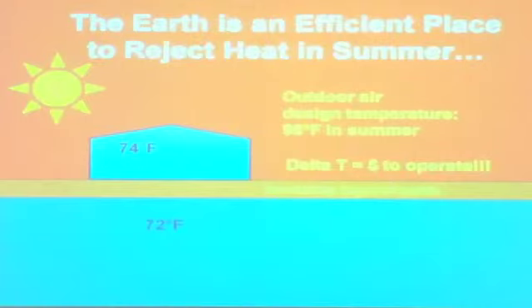Is that distance a function of the wells not sharing heat or isolating? Are you isolating the wells? Is that why you need so much? No, that's the thermal mass that it takes. Now the distance that you put those loops, the plastic tubes that were shown in that picture, the distance apart those are is based on the imbalance between the load profile of the building. The thermal mass is still the same. How far apart you put them is based on how imbalanced your loads are and how conductive the soils are, how fast heat moves in that particular soil. So it could be anywhere from, a long time ago, they were 10-foot centers, 20-foot centers, 30-foot centers. In some parts, if you get a totally imbalanced building, you get 60-foot centers.